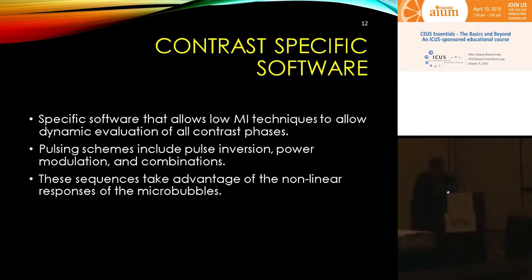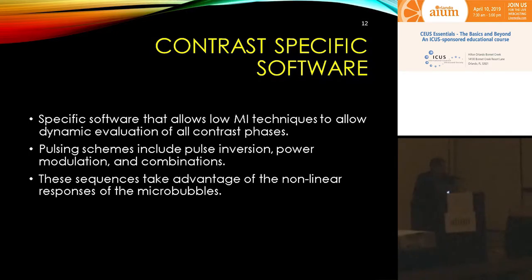Let me briefly go over the technical aspects again. We need contrast-specific software that allows low MI techniques for dynamic evaluation of contrast in all phases. There are pulsing sequences using pulse inversion, power modulation, and combinations — you don't have to understand these in depth. Most vendors have one or two different settings. The default setting is usually the best. They may have another setting — sometimes called CHI versus CPS — that may offer a little more resolution but not depth penetration. Start with the default and advance once you feel comfortable.